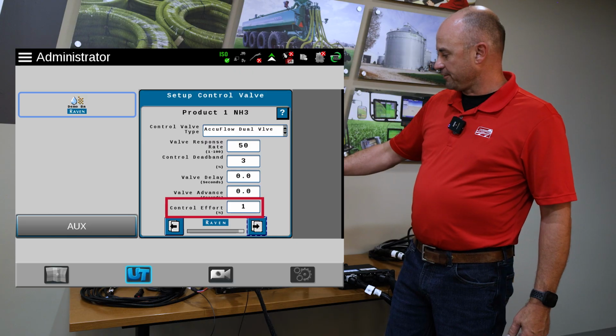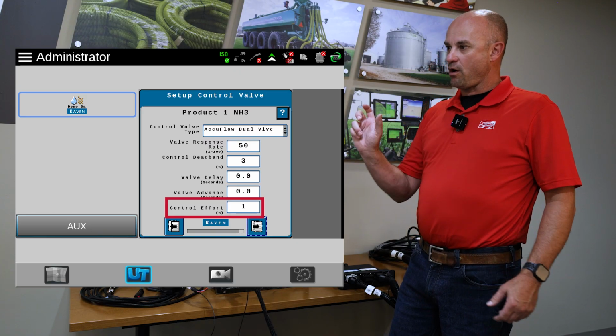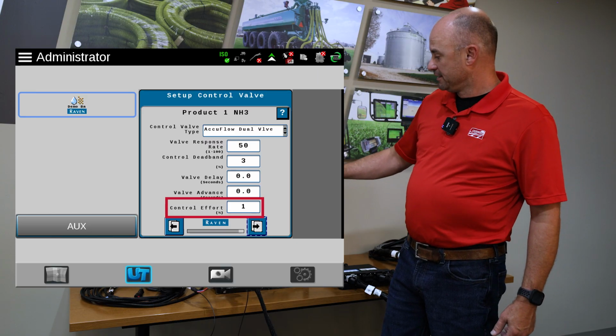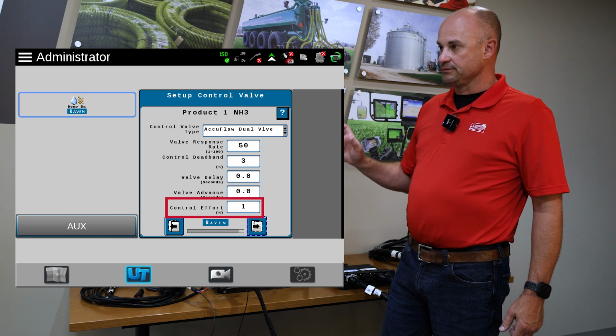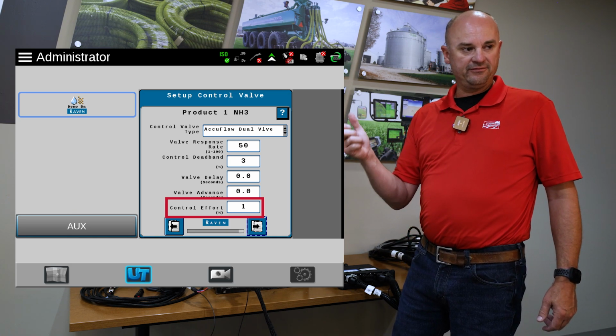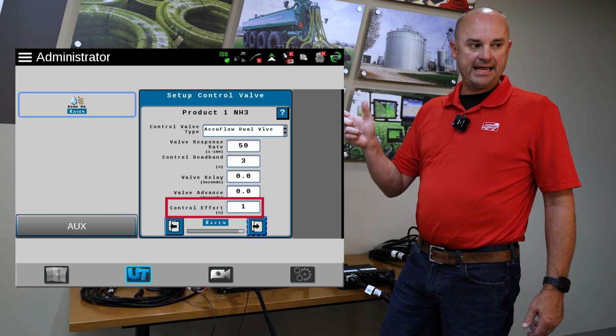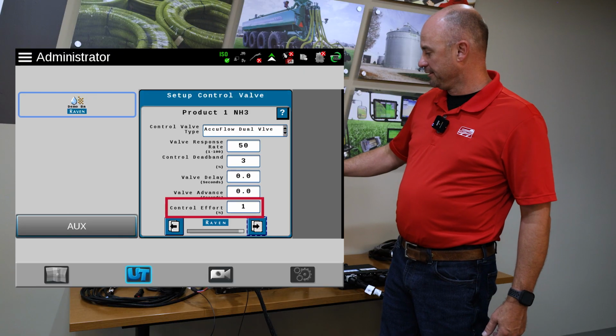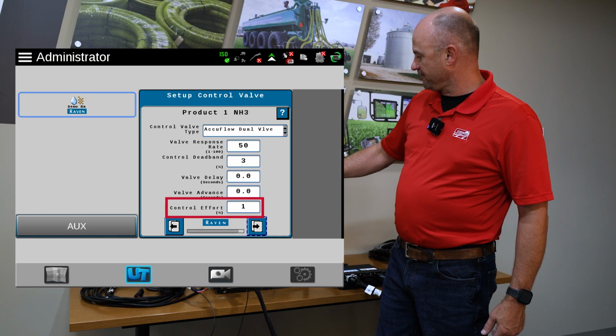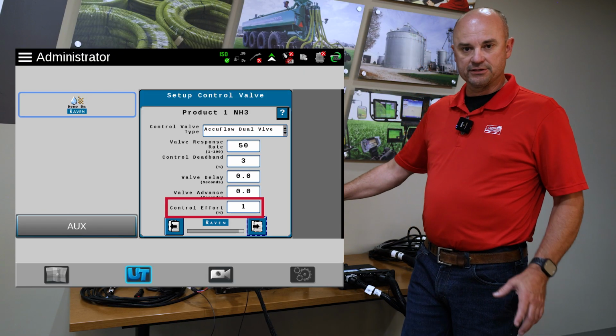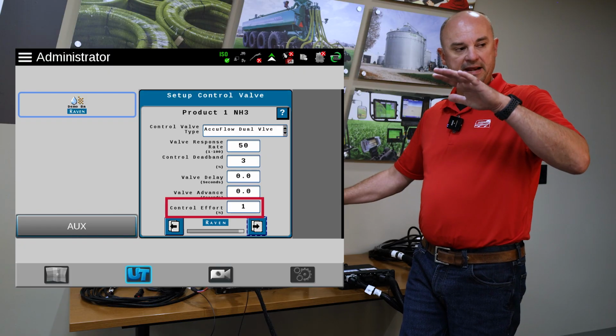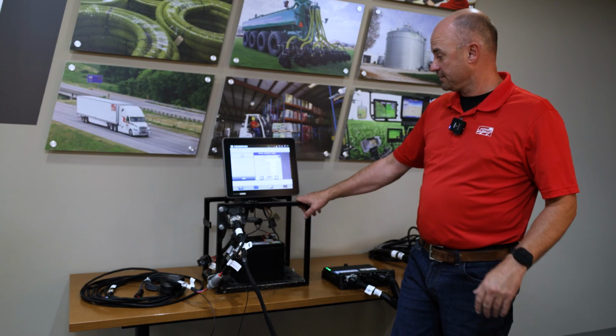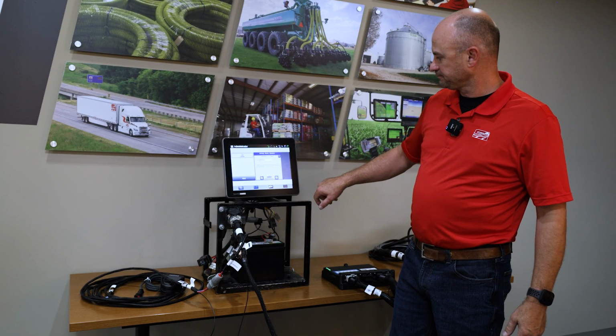Our control effort, what that is, is how hard it tries to turn the valve. So if your control valve is lazy and you don't think it's coming to rate fast enough, you raise it. If it's crazy and you can't get it to lock onto your rate, you lower that number. Typically, a starting number for this would be about 35%, which is a good place to start, and work up depending on your driving type and your conditions. We'll hit the next button.